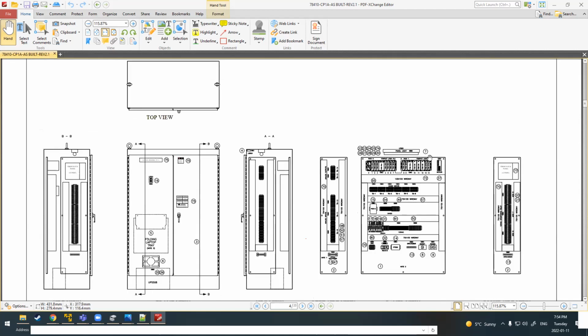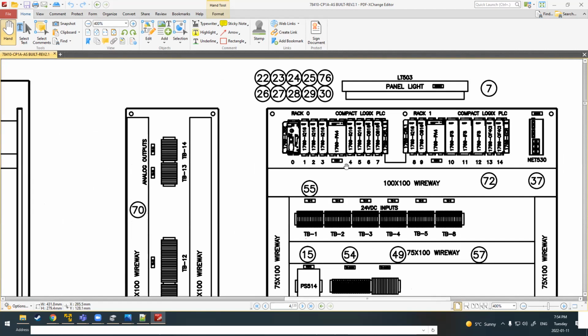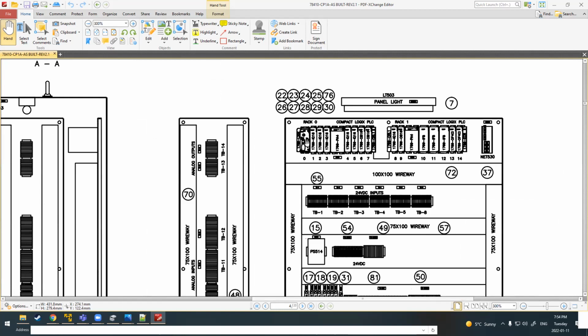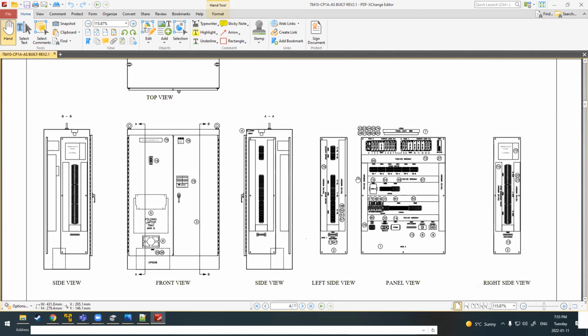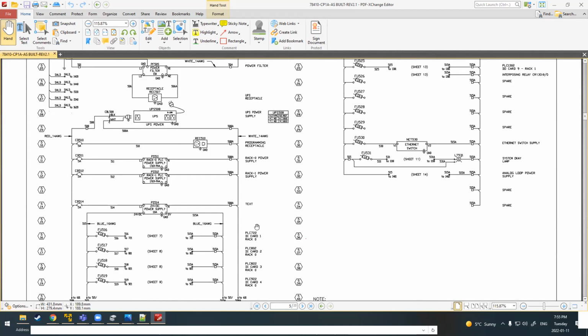We go back up here to the layout. You can see here we've got CompactLogix. We've got input cards. This is a power supply. This is that interconnection cable I was talking about. And that is another power supply. So if you were looking at these drawings and there was a problem that some of the cards weren't turned on, this is a drawing you would go to and go, okay, well, is CB512 tripped? You would use these for troubleshooting purposes.